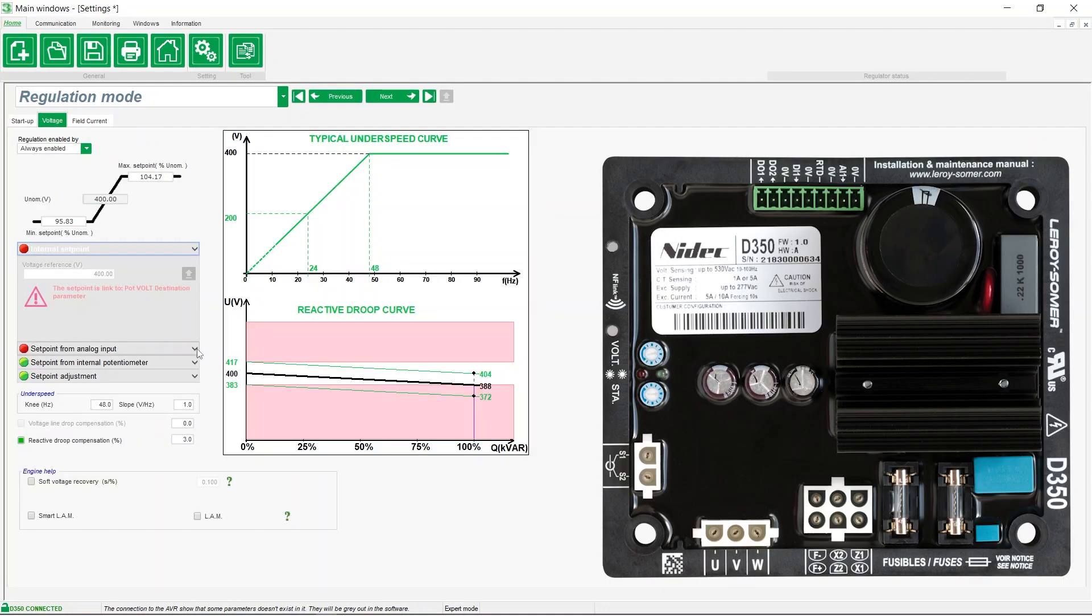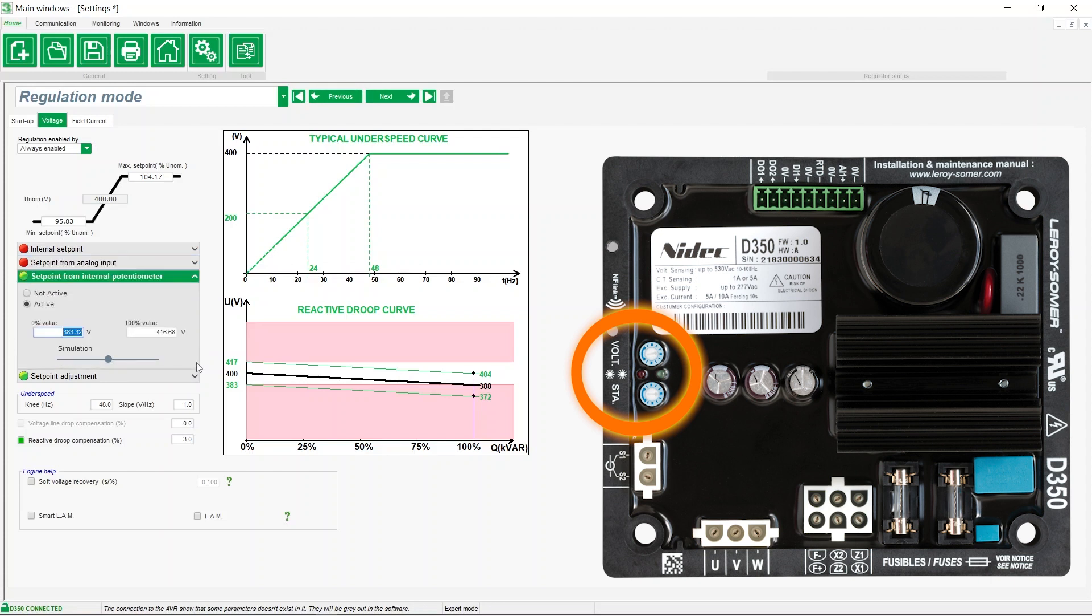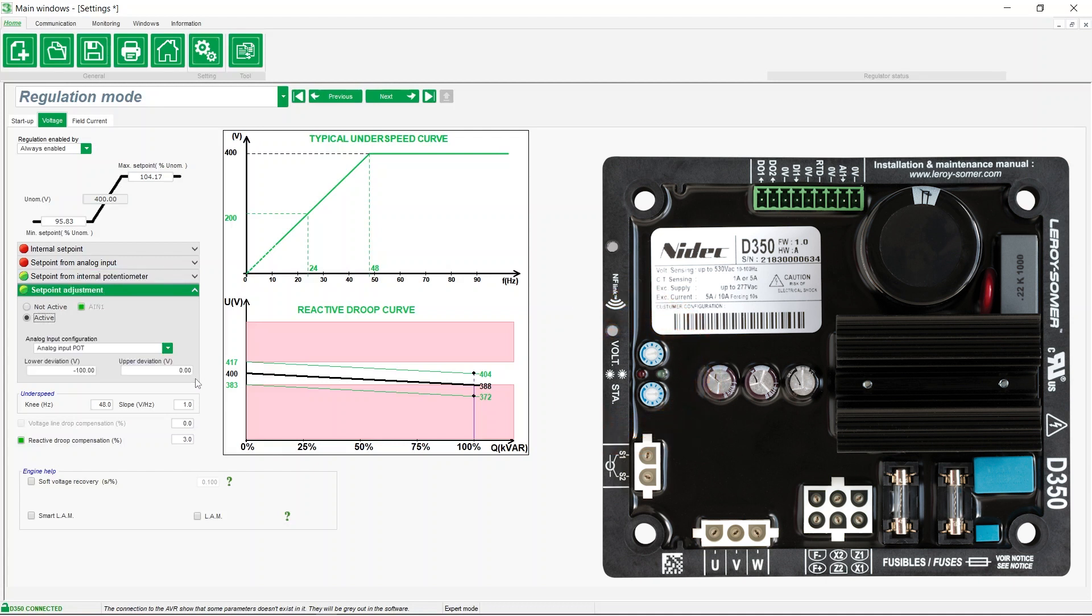By default, the internal potentiometers are enabled and assigned to voltage and stability. By making the internal potentiometer set point inactive, you can modify the voltage set point either by a predefined fixed value or an analog input.